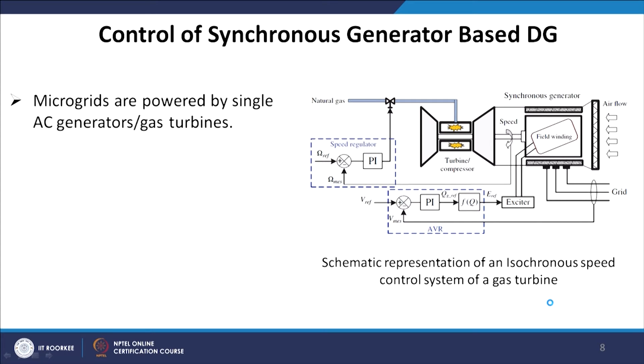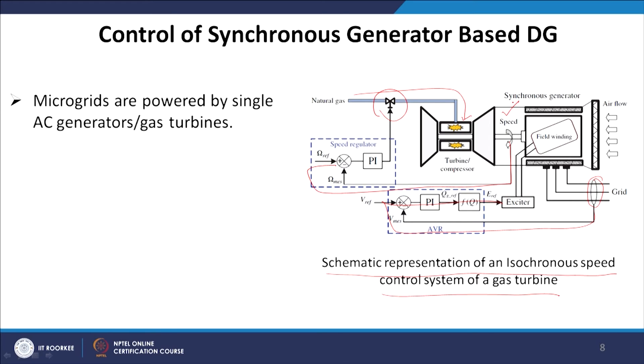Control of synchronous generator-based distributed generators is as straightforward as thermal power generators. A simple schematic of a speed control system for a gas turbine shows natural gas flowing to generate power for the grid. The grid inputs are fed to the exciter, and the speed signals can vary through a speed regulator so that natural gas injection can vary to meet the desired speed. You detect the speed, and based on your input energy source — whether steam or gas — you can adjust speed to achieve the desired frequency.